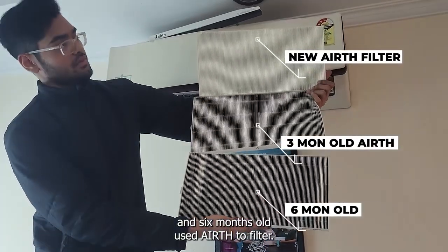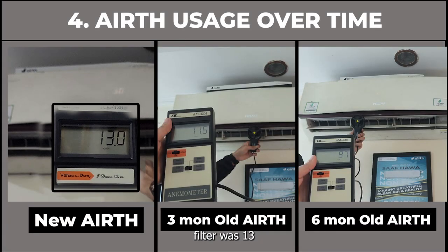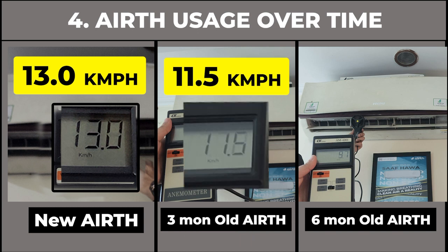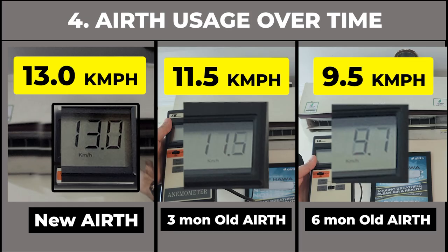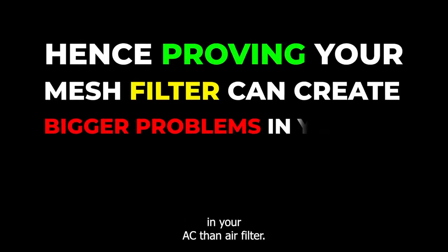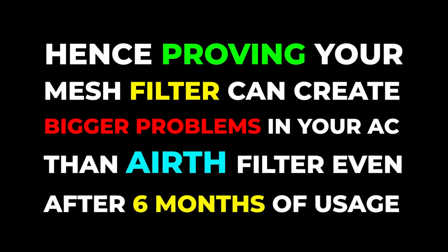But before that, let's complete our last experiment. We tested new, three-month, and six-month-old used Airth filters. The airflow with a new Airth filter was 13; with a three-month used filter it was 11.5; and with a six-month-old Airth filter the airflow reduced to 9.5 from 13. This proves your mesh filter can create bigger problems in your AC than an air filter, even after six months of usage.